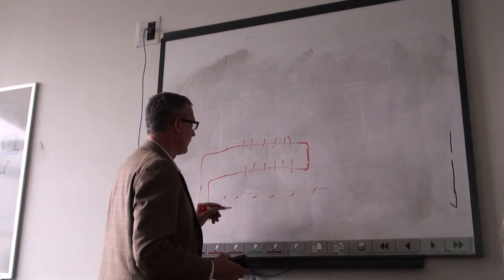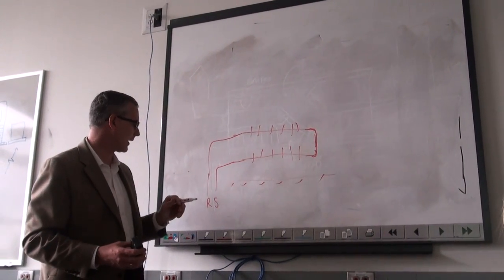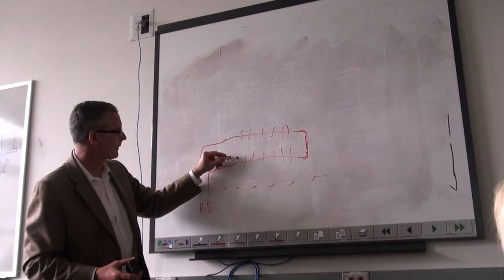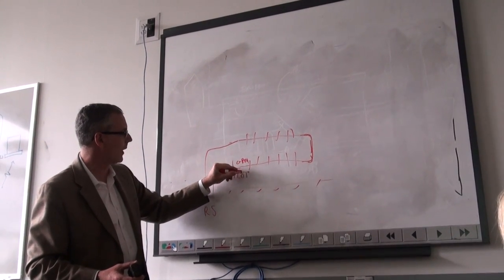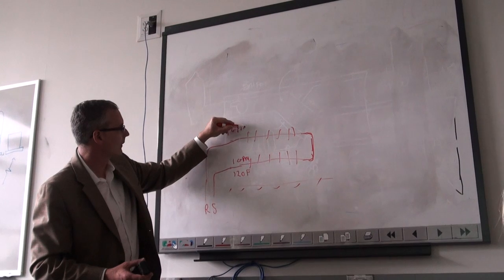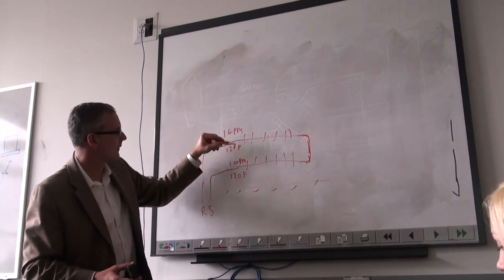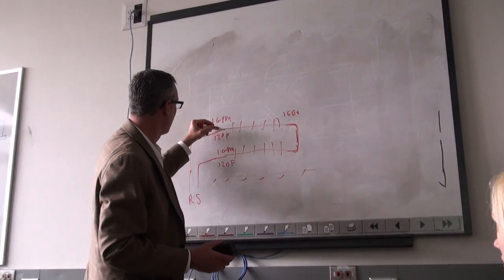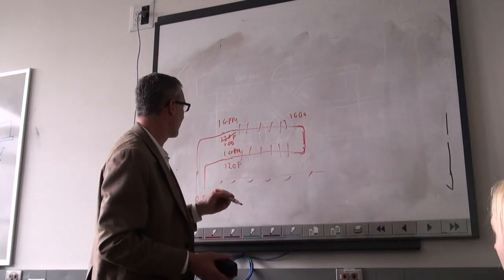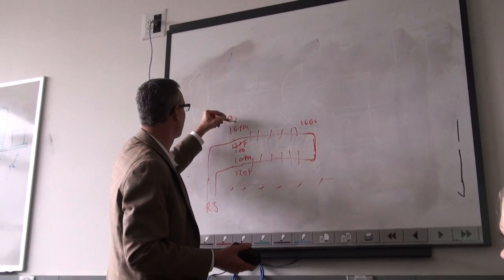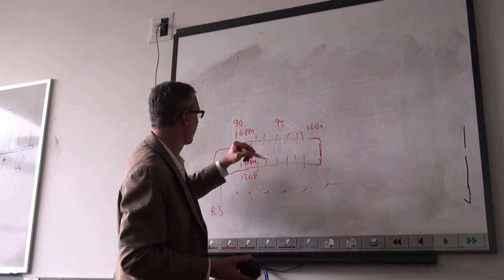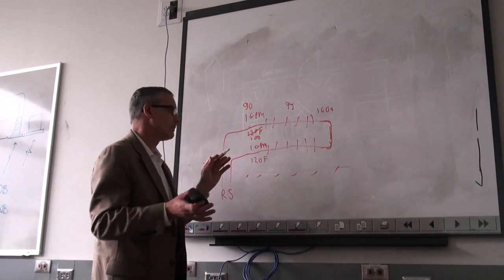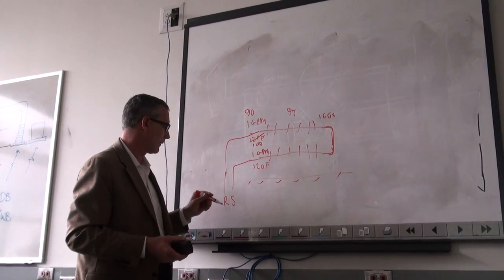The engineer will care because he won't get the load that he thought he was going to get out of this thing, because our software is simulating 1 GPM at, in this case, 120 degree entering water on both tubes. Now, if he does this, he'll have 120 here. He might have 100 here, so this isn't 120 anymore, it's 100. So his average water, if he leaves at 90, would be 95. Well, the program is assuming 110 average water. So loads are off, no one's happy, and no one knows why.